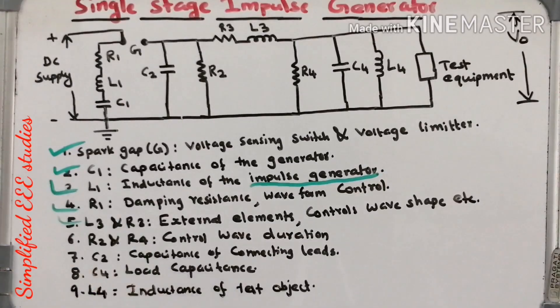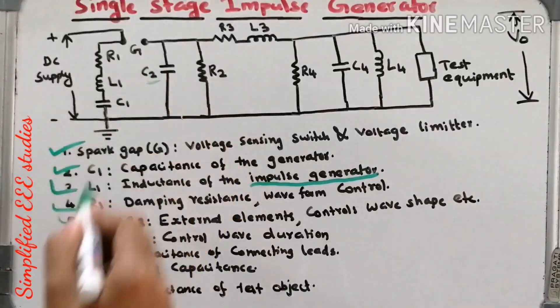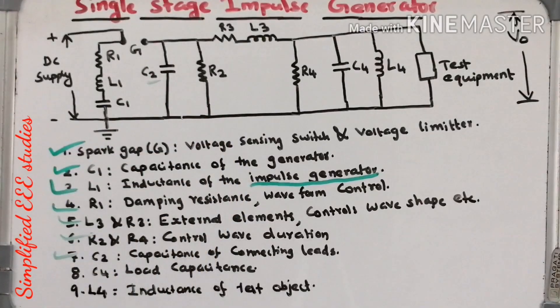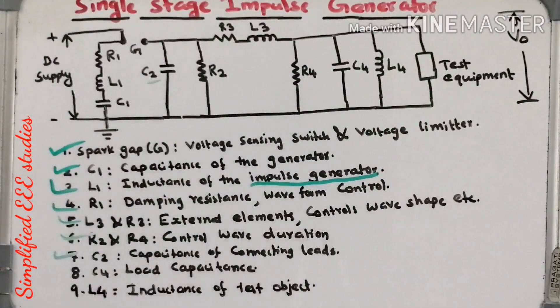R2 and R4 function to adjust the wave front as well as wave tail time. By selecting suitable values of R2 and R4, it is easy to control wave front as well as wave tail. C2 is the capacitance of connecting leads. The capacitance due to connecting leads or external elements is generally known as parasitic capacitance; C2 represents this parasitic capacitance. C4 is the load capacitance related to the test object.